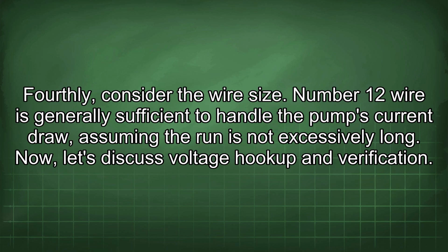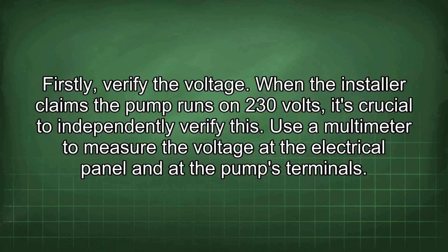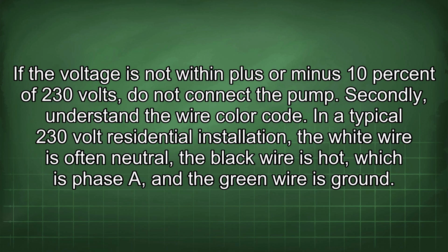Fourthly, consider the wire size. Number 12 wire is generally sufficient to handle the pump's current draw, assuming the run is not excessively long. Now let's discuss voltage hookup and verification. Firstly, verify the voltage. When the installer claims the pump runs on 230 volts, it's crucial to independently verify this. Use a multimeter to measure the voltage at the electrical panel and at the pump's terminals. If the voltage is not within plus or minus 10% of 230 volts, do not connect the pump.